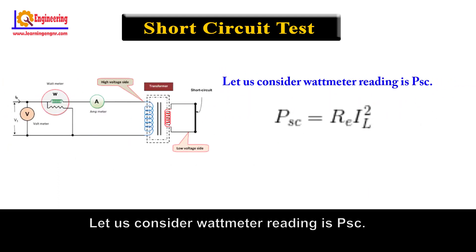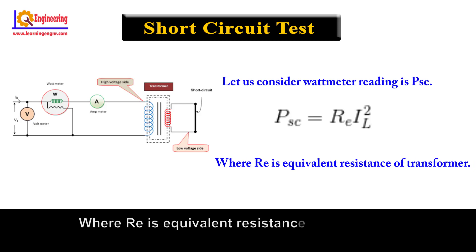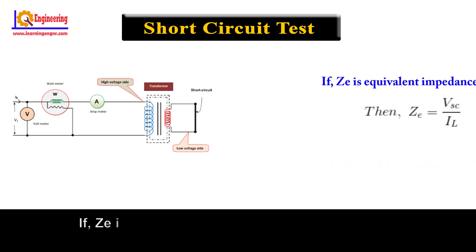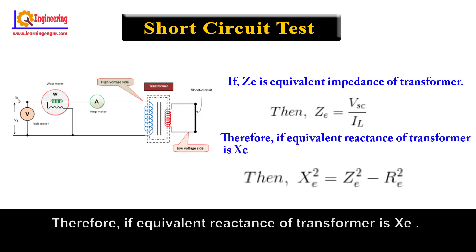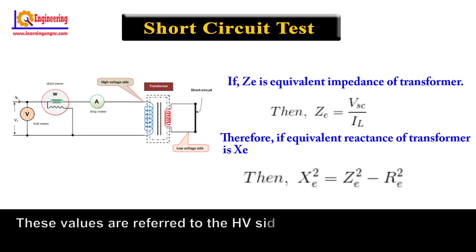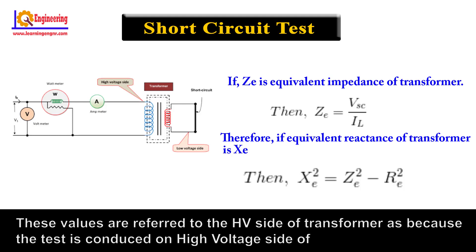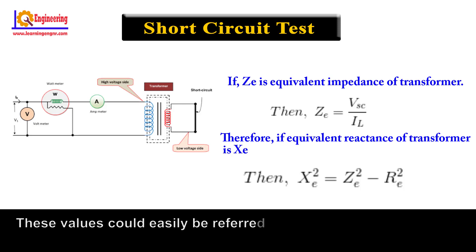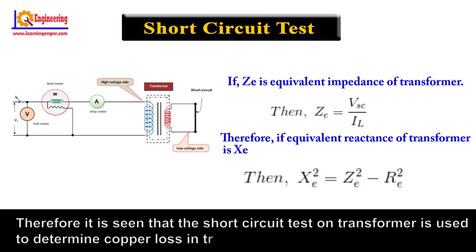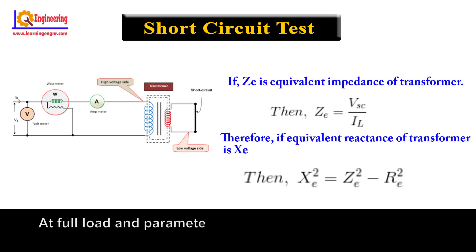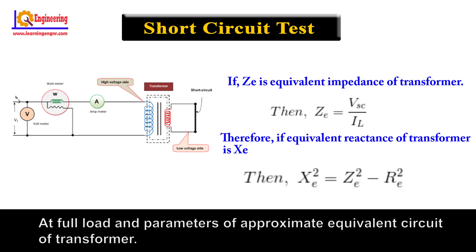Let us consider the wattmeter reading is PSC, where Re is the equivalent resistance of the transformer and Ze is the equivalent impedance of the transformer. These values are referred to the high voltage side of the transformer, as the test is conducted on the high voltage side. These values could easily be referred to the low voltage side by dividing these values with the square of the transformation ratio. It is seen that the short circuit test on transformer is used to determine copper loss in transformer at full load and the parameters of the approximate equivalent circuit of transformer.